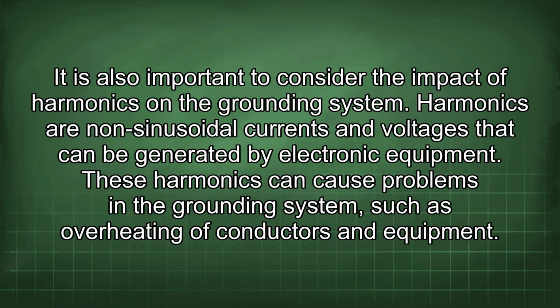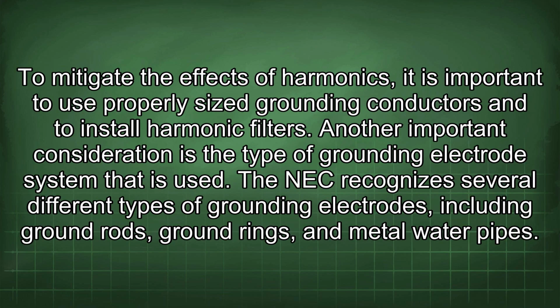It is also important to consider the impact of harmonics on the grounding system. Harmonics are non-sinusoidal currents and voltages that can be generated by electronic equipment. These harmonics can cause problems in the grounding system, such as overheating of conductors and equipment. To mitigate the effects of harmonics, it is important to use properly sized grounding conductors and to install harmonic filters.